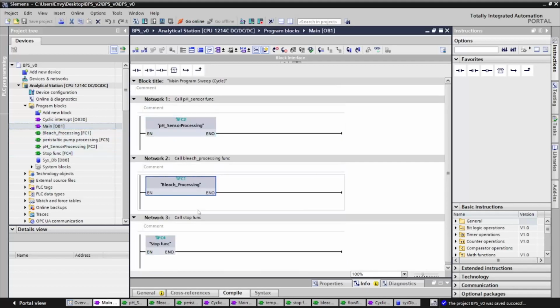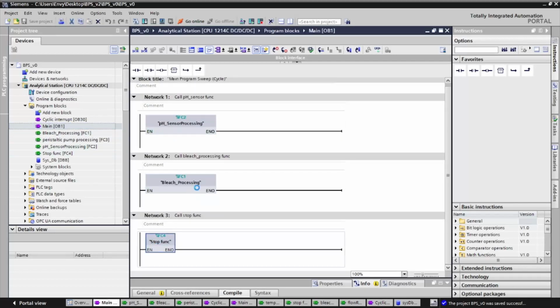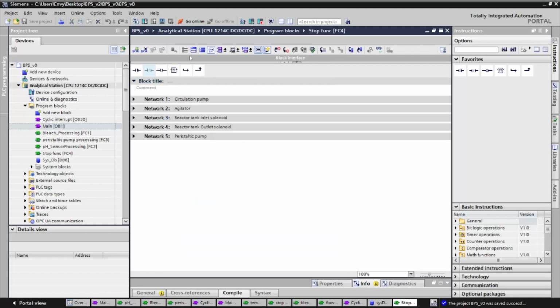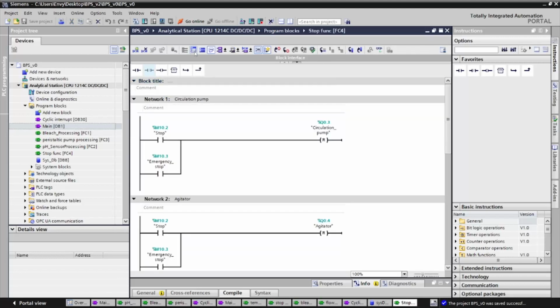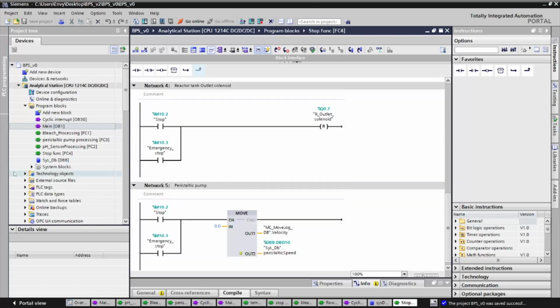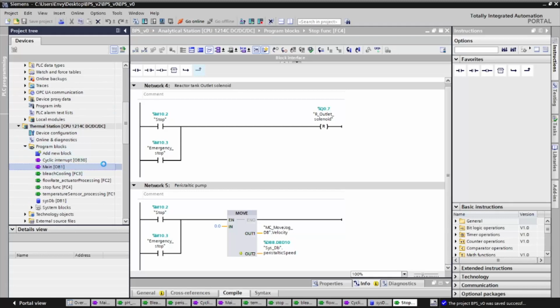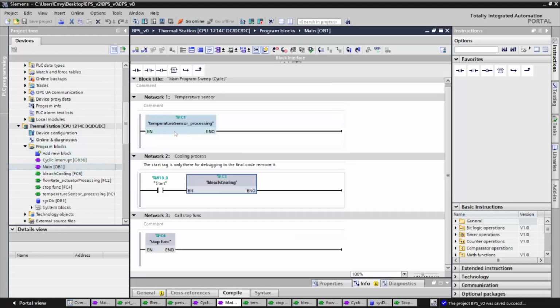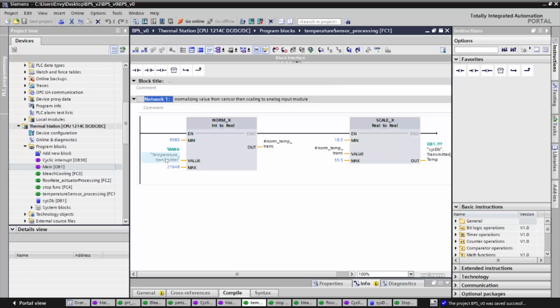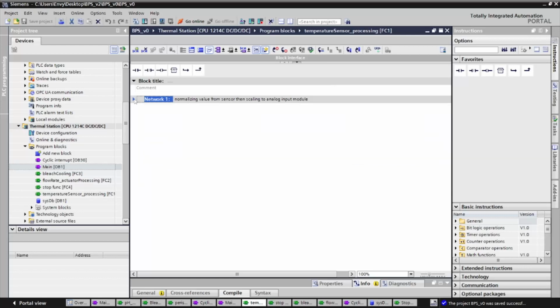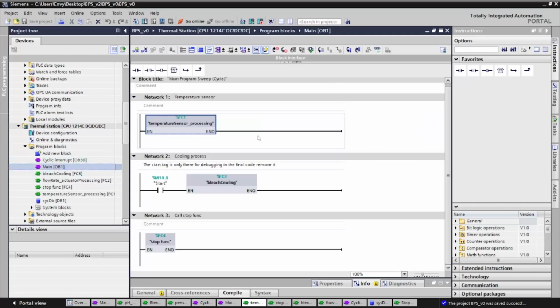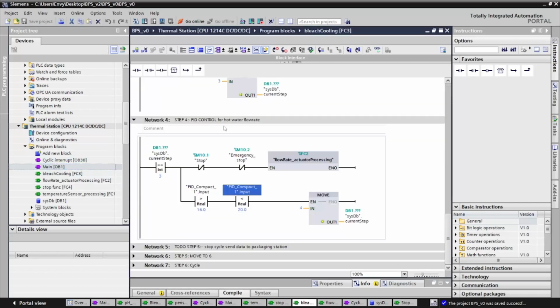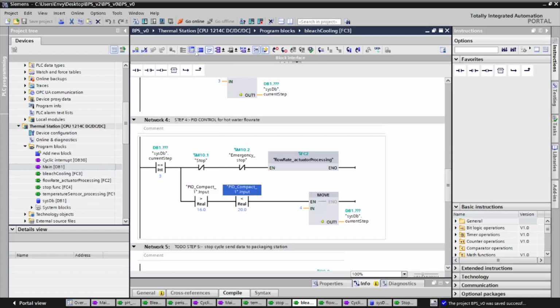And for safety reasons, we have a stop function that's used to stop the process whenever the operator presses either the stop or emergency buttons. On the thermal station, on the main OB, on the first network, I'm calling in the temperature transmitter, which monitors the temperature of the bleach. And on the second network is where the cooling actually happens.